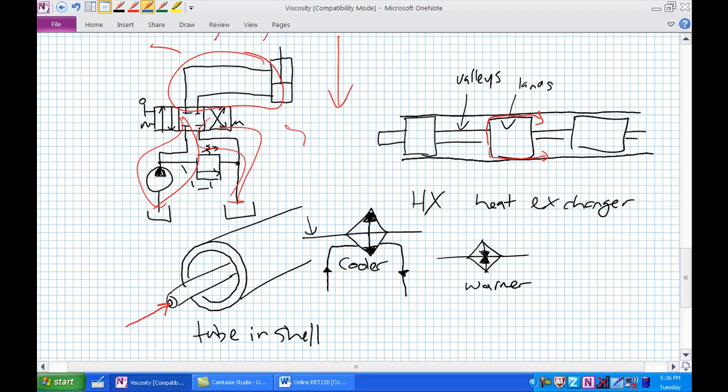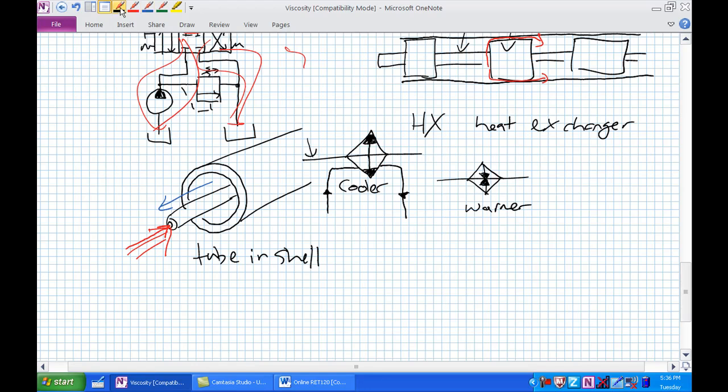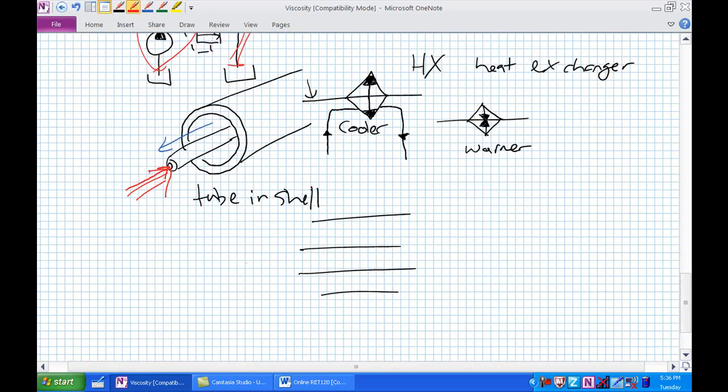And now here's a tricky question. If hot hydraulic fluid is coming in this direction, which direction is the cool fluid coming in and out? The answer is opposite direction. Okay, the way to think about this is, here are our passageways, here's our side view. Here's our extremely hot hydraulic fluid right about here, extremely hot as it enters the heat exchanger. It's progressively cooling down.